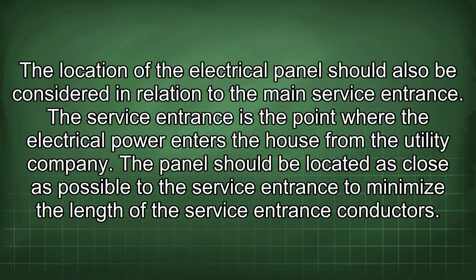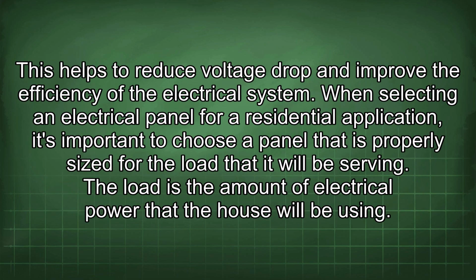The location of the electrical panel should also be considered in relation to the main service entrance. The service entrance is the point where the electrical power enters the house from the utility company. The panel should be located as close as possible to the service entrance to minimize the length of the service entrance conductors. This helps to reduce voltage drop and improve the efficiency of the electrical system.